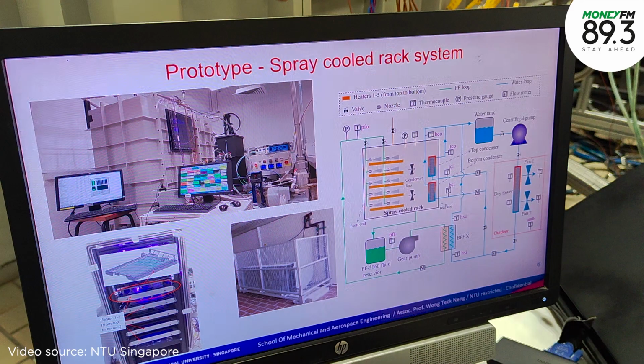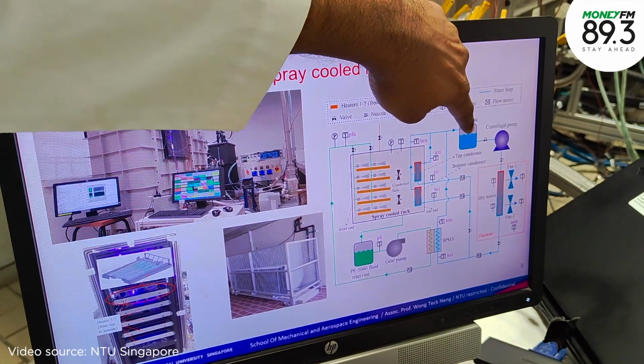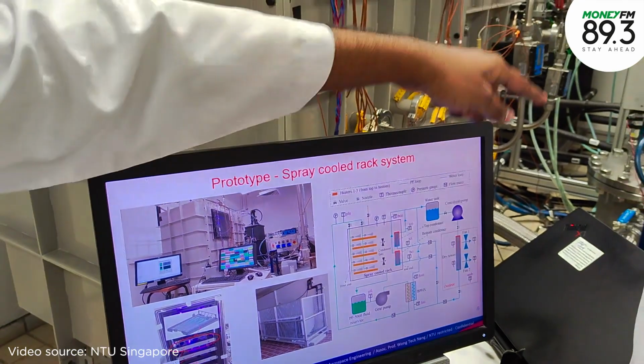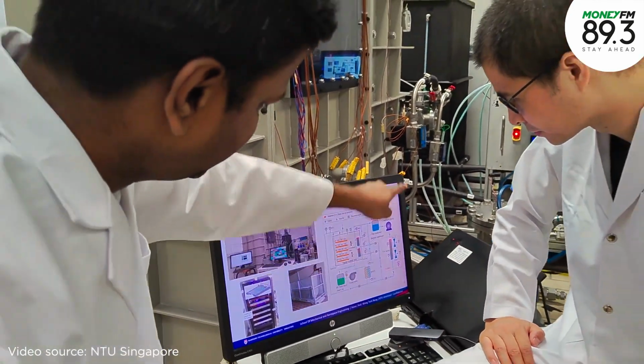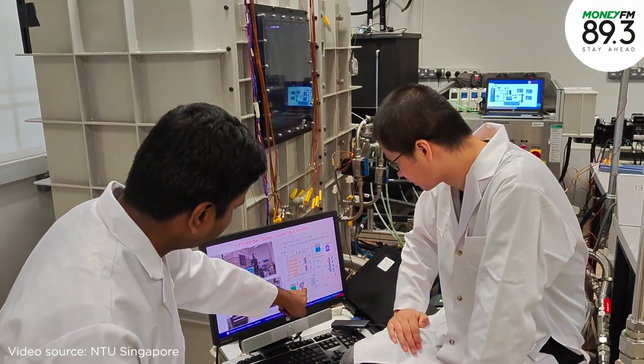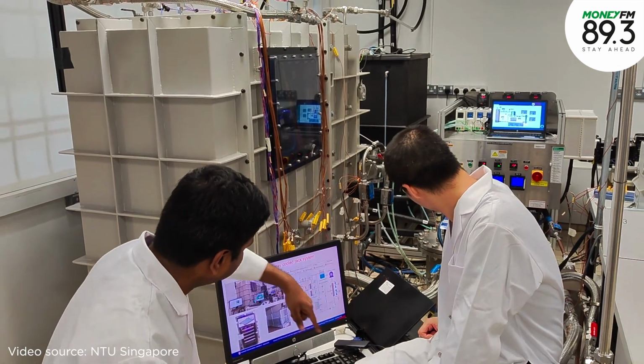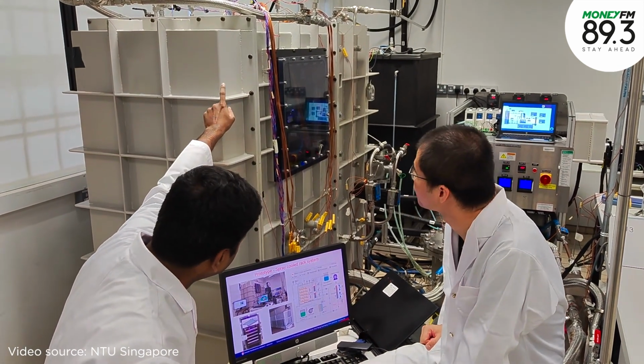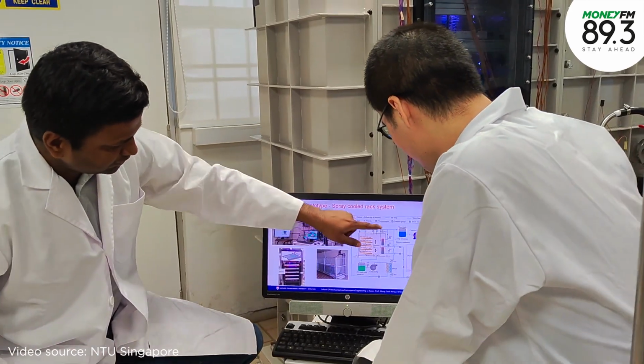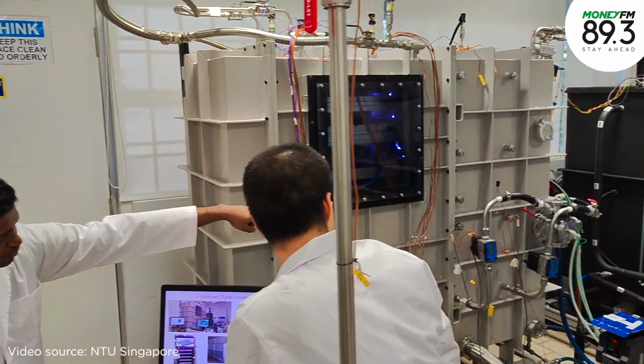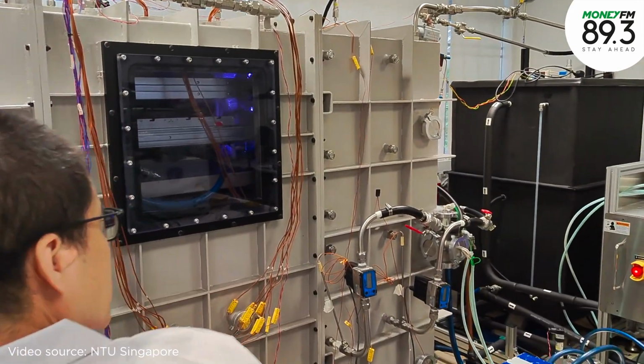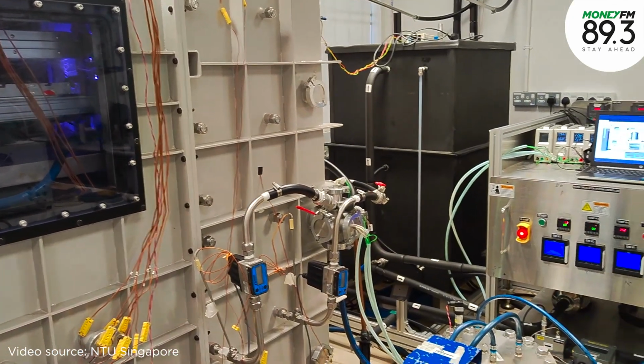And how will this actually translate into higher efficiency for data centers, as your team has claimed? Because the CPU is able to operate at a lower temperature without the need for a chiller, this spray cool system also allows a higher IT load density, since it increases heat rejection capability and allows higher computational performance per unit space.